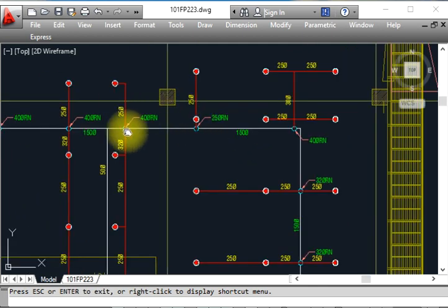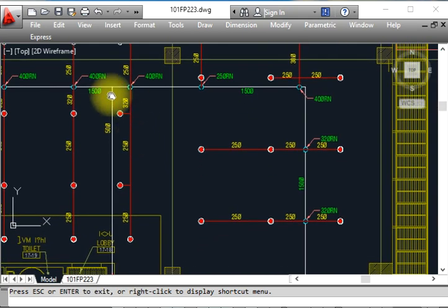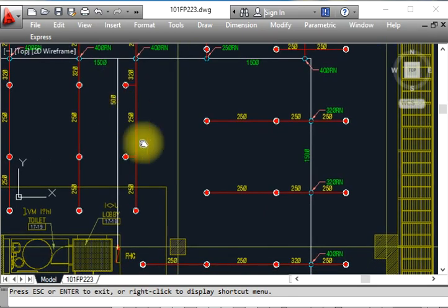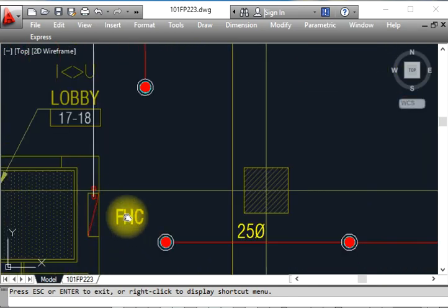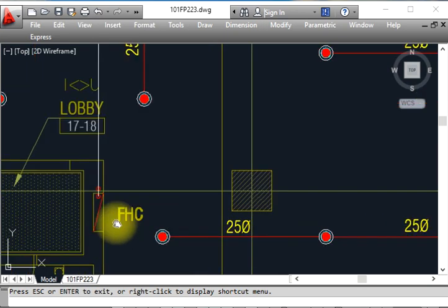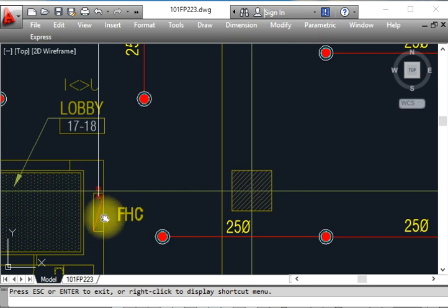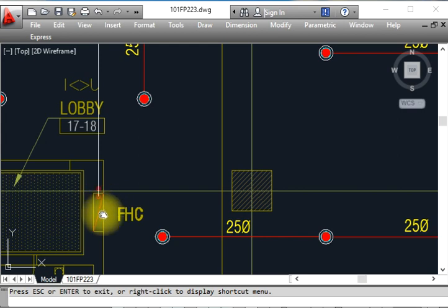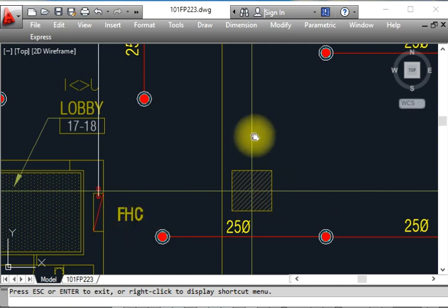This white line is the main line. This 2-inch pipe is going for the fire hose cabinets — this is a fire hose cabinet here. I already made a video for this. Basically a fire hose cabinet is used on every floor. Inside the cabinet we keep a hose reel cylinder, and there is also a pipe hose — maximum 30 meters of pipe hose as per NFPA.